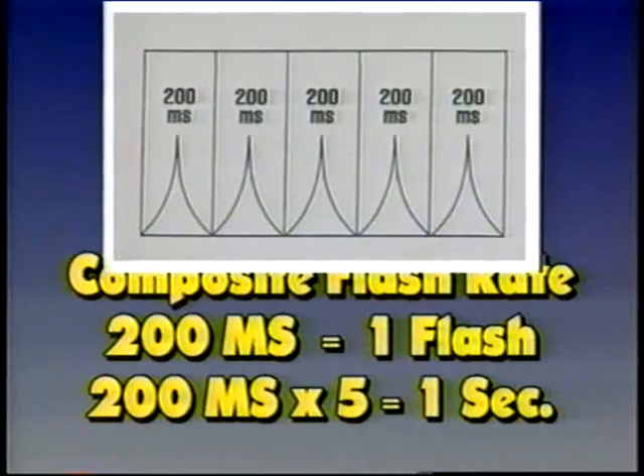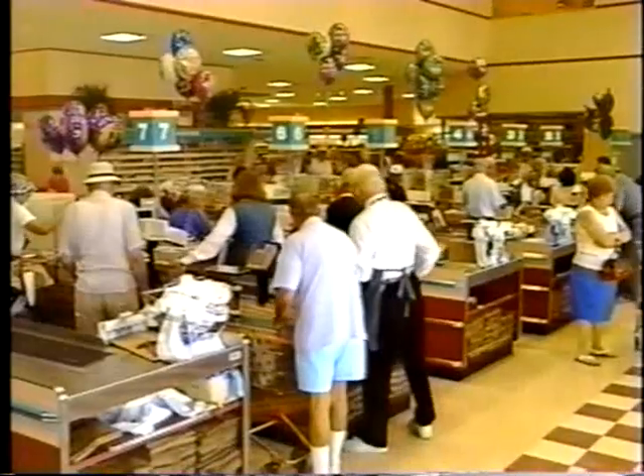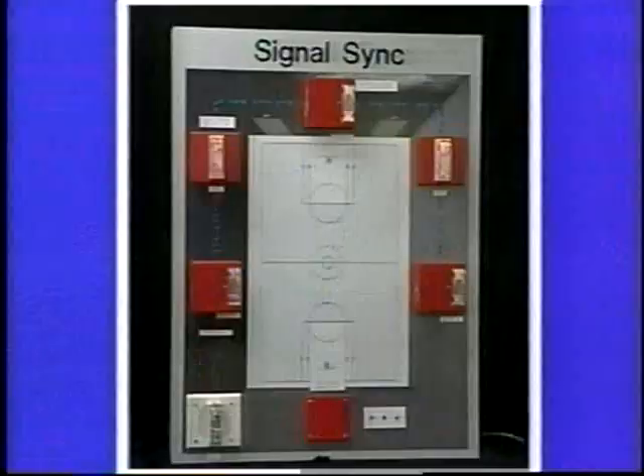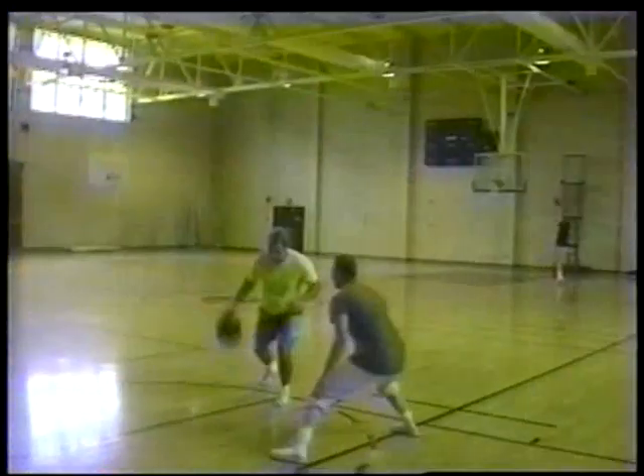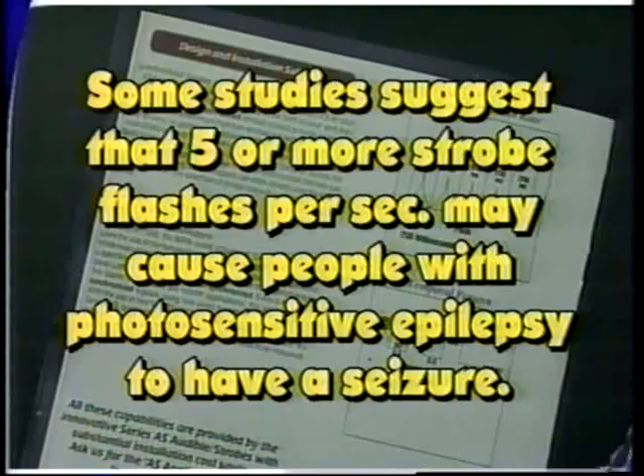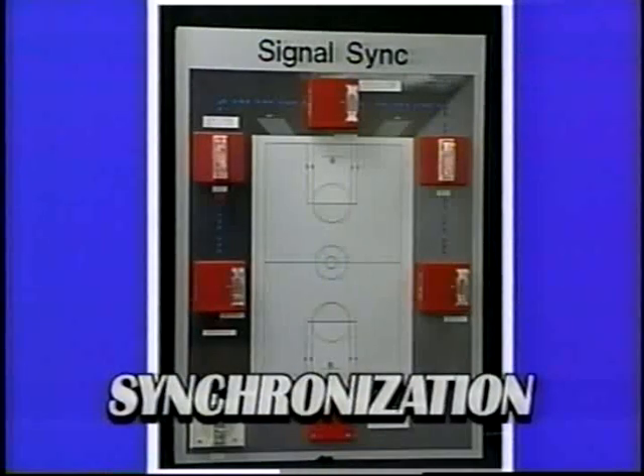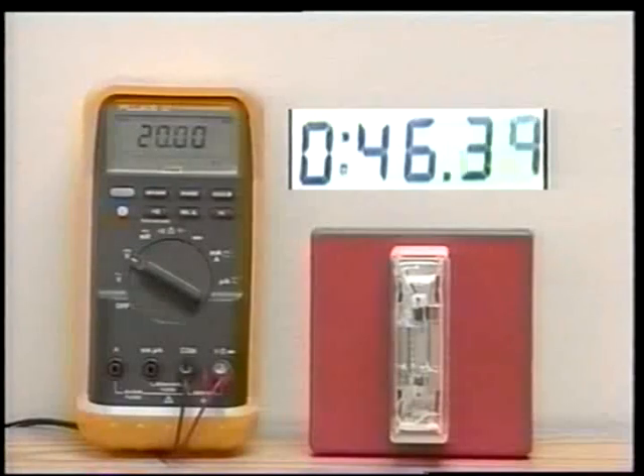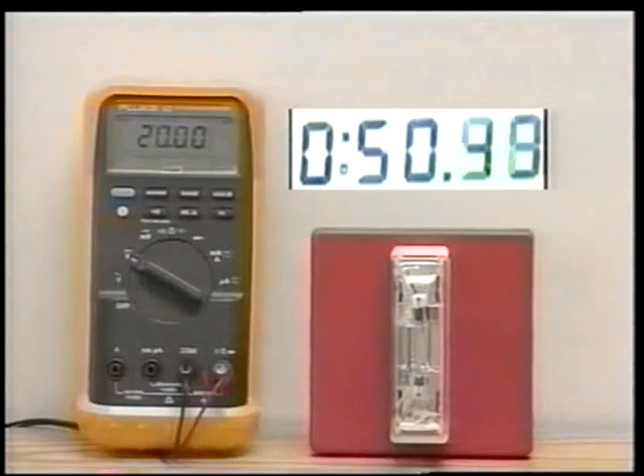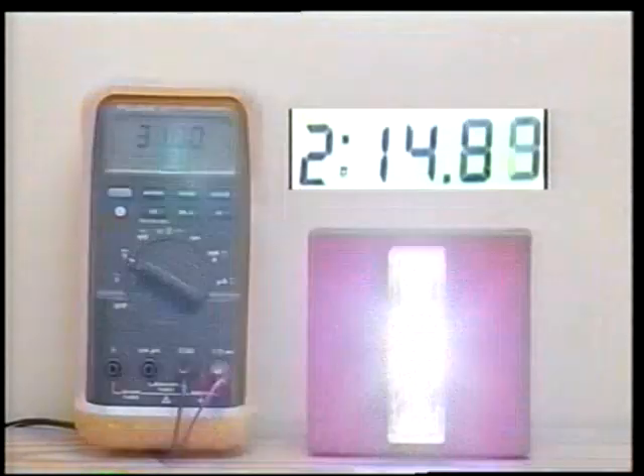In the case of synchronized strobes, ADA recommends that the composite flash rate not exceed five flashes per second for multiple strobes installed in the field of view, such as in a supermarket. The ADA guidelines also indicate that the use of synchronized strobes is an acceptable solution when more than two strobes are installed in the same field of view, such as in a gymnasium or a hallway. Some studies suggest that five or more strobe flashes per second may cause people with photosensitive epilepsy to have an epileptic seizure. Non-synchronized strobes flash randomly and may interact to produce this rate, while synchronized strobes flash in unison at a fixed rate, thus helping to avoid this concern.